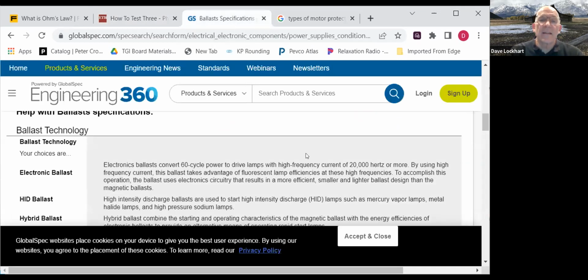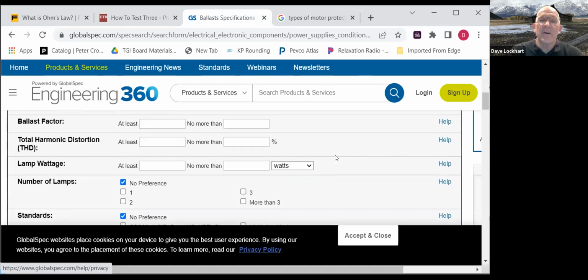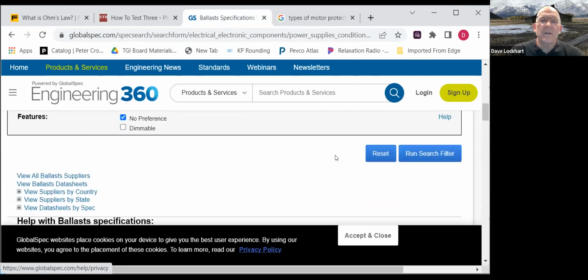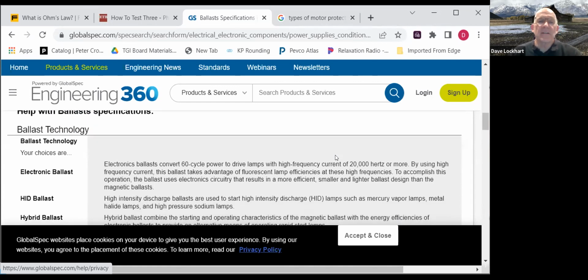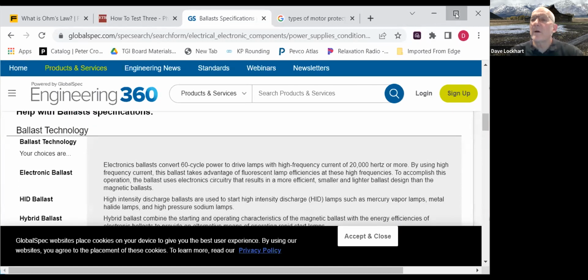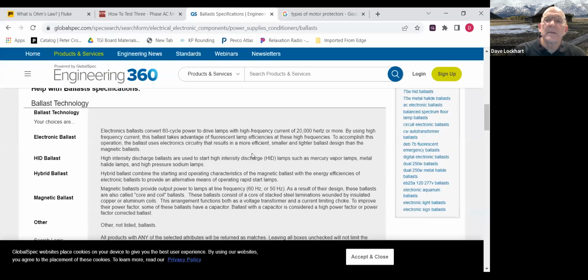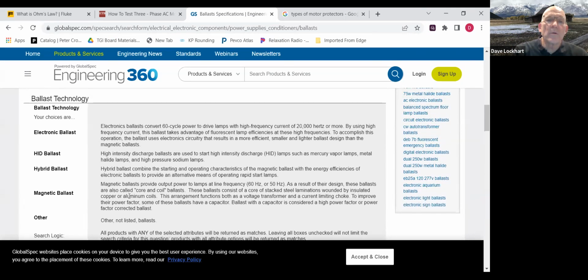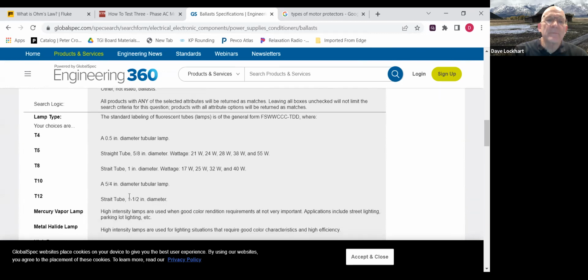Here we've got the lighting circuit. Let me go into here. It started right here, with different types of ballast technology. Some of you may be very familiar with electronic ballast, which converts 60 cycle power to drive the lamps at a high frequency of 20,000 hertz or more. Using the high frequency currents, the ballast takes advantage of the fluorescent lamp efficiencies. We've also got HID ballast, hybrid ballast, and magnetic ballast. Those are the common ballast types.